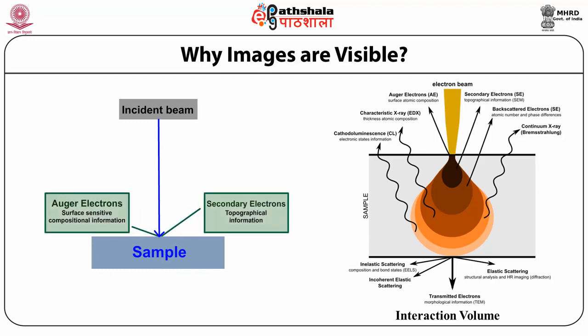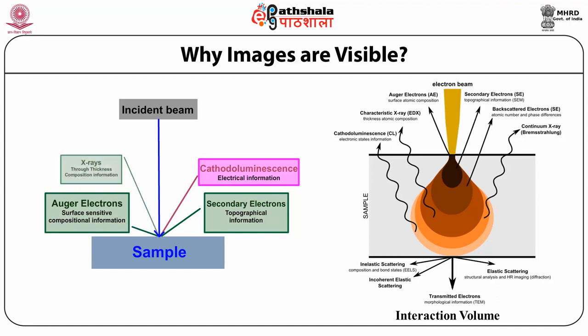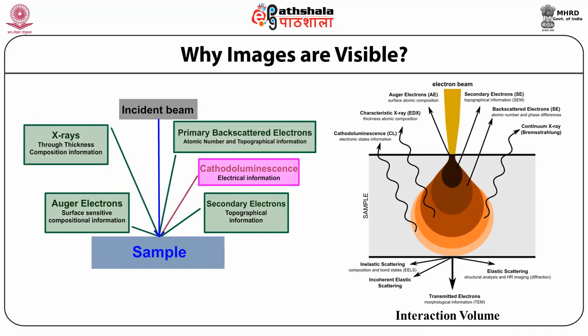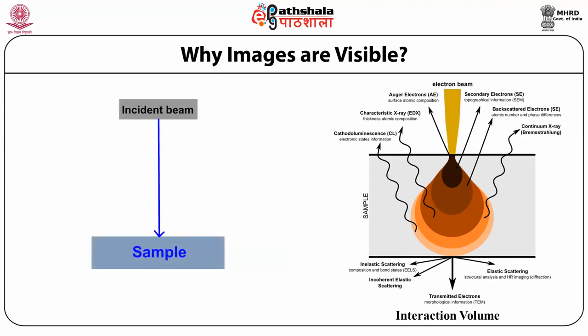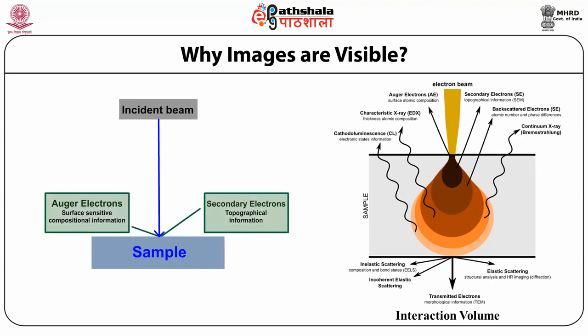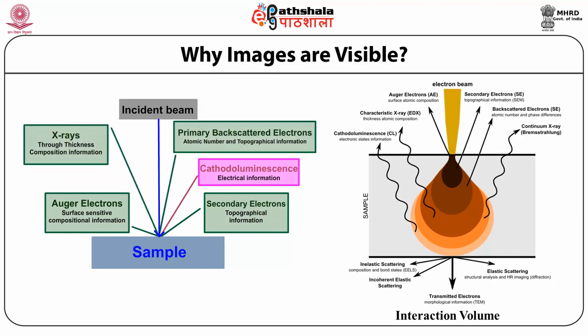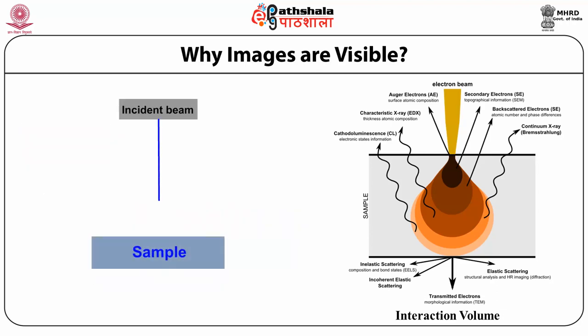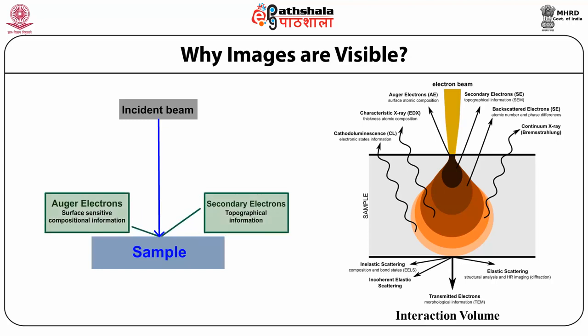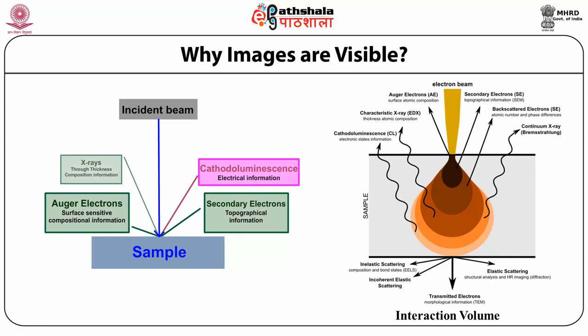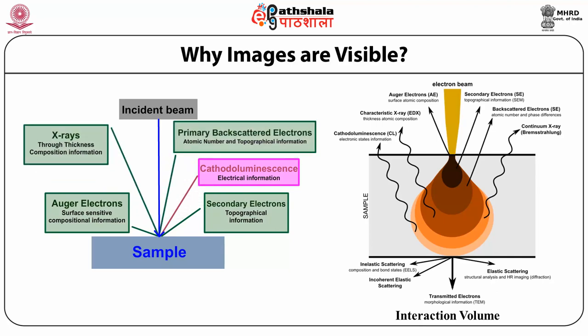Electronic amplifiers are used to amplify the signals, which are displayed as variations in brightness on a computer monitor or, for vintage models, on a cathode ray tube. Each pixel of the computer video memory is synchronized with the position of the beam on the specimen, and the resulting image is a distribution map of signal intensity emitted from the scanned area. In older microscopes, the image may be captured by photography from a high-resolution cathode ray tube, but in modern machines they are digitized and saved as a digital image.